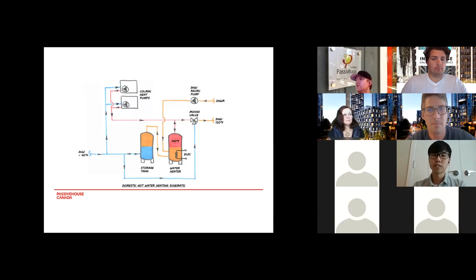The second point is redundancy, which we had to consider now that we'd introduced a centralized system. I put in 2 Colmac heat pumps, each sized for 50% of the load, so that if one went down for maintenance, we'd still have 50% of the capacity to serve the building. I also had an electric water heater to supplement the Colmac heat pump in case one went down and the remaining heat pump wasn't keeping up with demand.